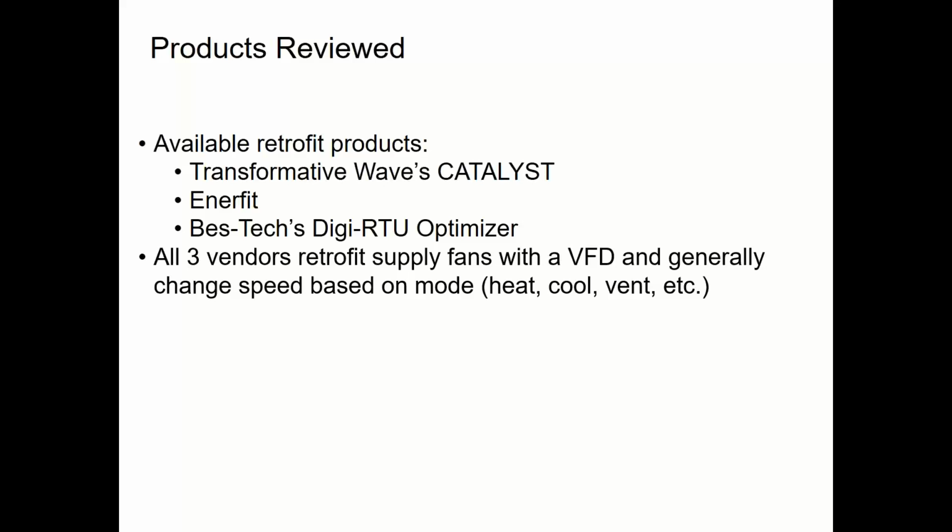If you didn't realize it, the residential equipment has a significantly higher manufacturing volume than commercial equipment, so a lot of R&D money goes into that residential stuff. And then a lot of R&D money goes into the big chiller plants, because chiller plants are controlling huge giant buildings. They're exciting. It's easy to get an end user to understand a payback scenario and do it. That middle group with the rooftop units, they get no R&D dollars. Nothing. Well, not nothing, I'm exaggerating, but they basically wait for something cool to happen in residential and then they bring it up, or they wait for something cool to happen in large commercial and then they bring it down into the rooftops. So in any case, this is a pretty well-defined sequence of operation for a residential ECM furnace, and using this VFD is just a way to bring it into the rooftop world.